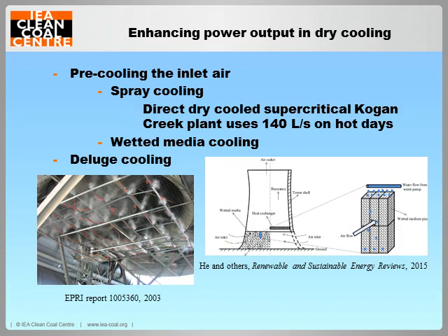Wetted media is less common than spray cooling. Here, the inlet air is cooled and humidified by direct contact with water as it passes through the wetted medium at the base of the dry cooling tower. And this is shown in the right-hand figure. Excess water is collected and recirculated. Both these methods cool the air to near its wet bulb temperature, which improves the performance of the air-cooled condenser, and they're only operated on hot days.